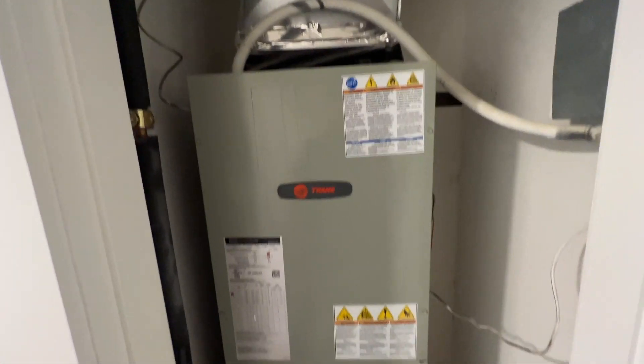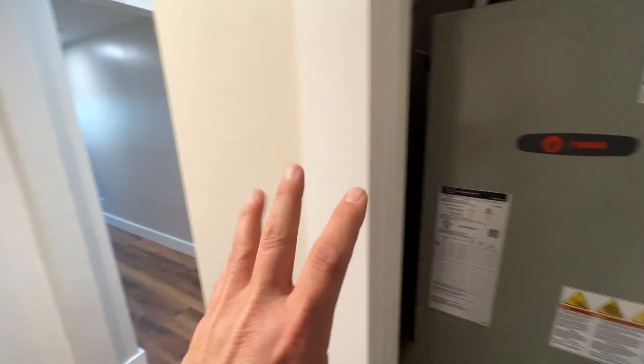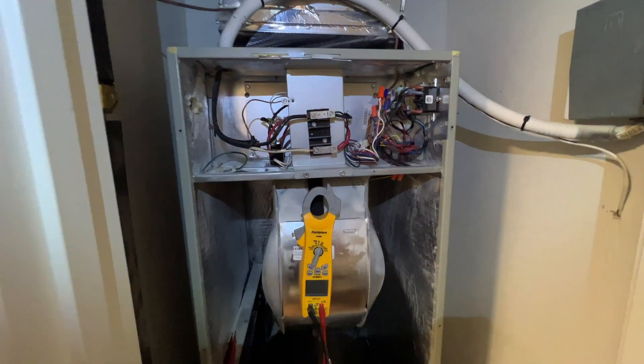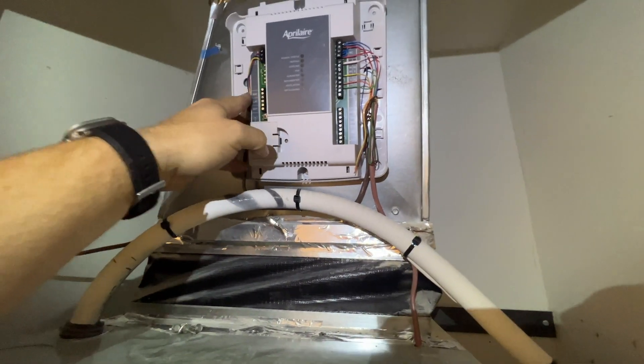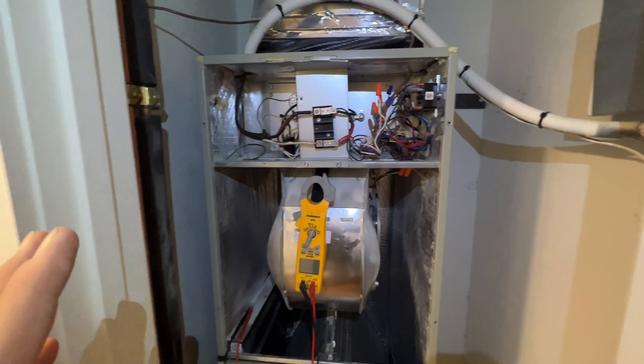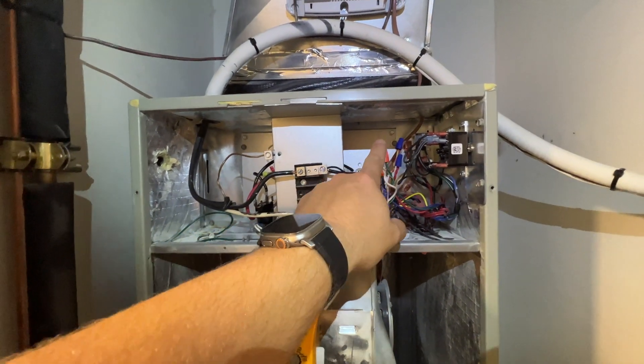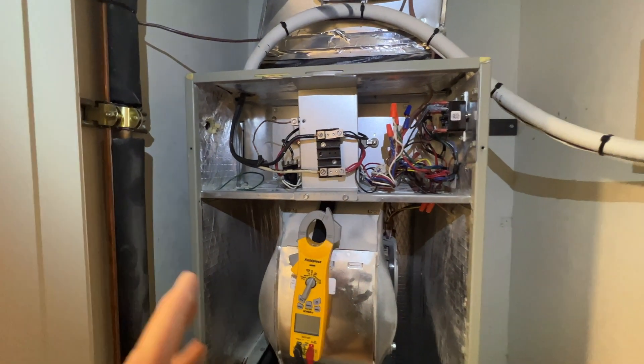Here's the system we're working on. We can probably mount the module here so we can actually see it. We're going to go ahead and get everything unwired and put in a new thermostat down the hall. Alright, I got everything pretty much cleaned up and mounted the module up here. Everything is now nice and clean when it comes to the low-volt wiring — nice and simple. The thermostat is already mounted. We're going to go up to the condenser now and verify the wiring is correct up there, because I'm pretty sure they did not have the W2 wire coming back to turn on the electric heat whenever it goes into defrost mode. I'll make sure that's connected and that all the wiring color coding is good to go.